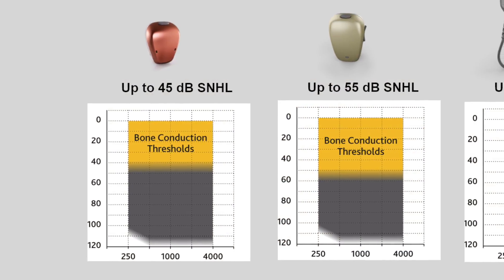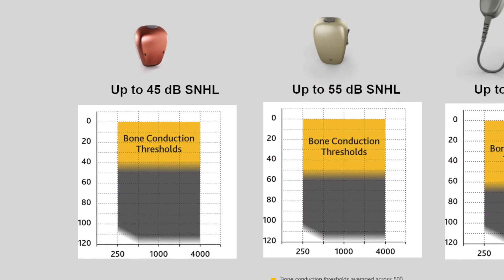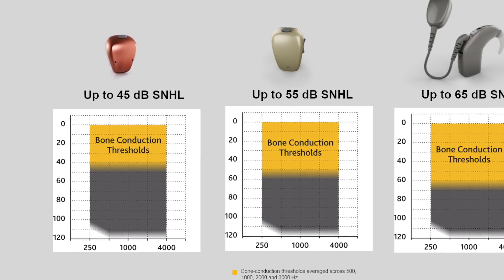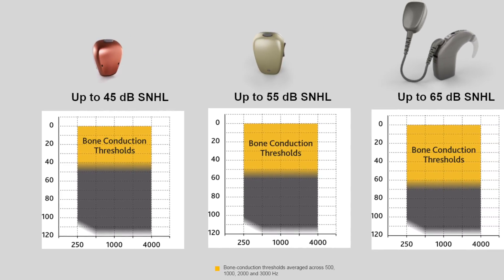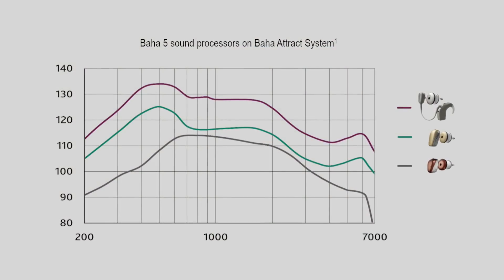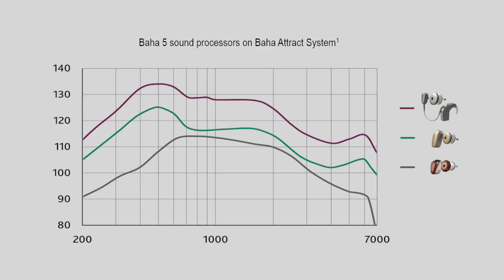Where the Baha 5 processor fits patients with up to 45 decibels of sensorineural hearing loss, the Baha 5 Power expands that to patients with a 55 decibel sensorineural hearing loss. This allows us to move patients from one processor to another if their hearing changes over time.